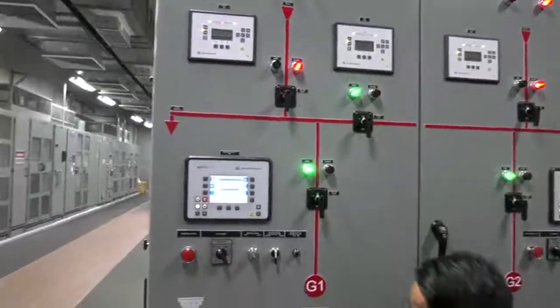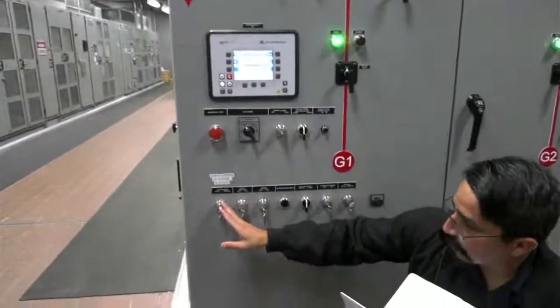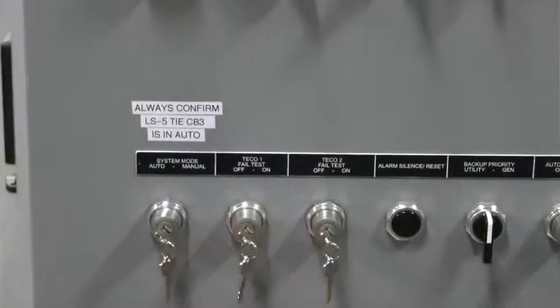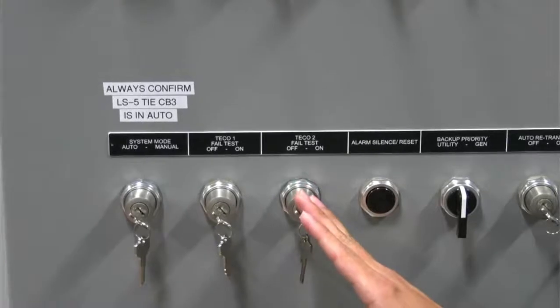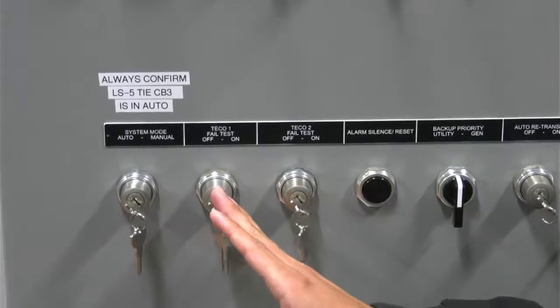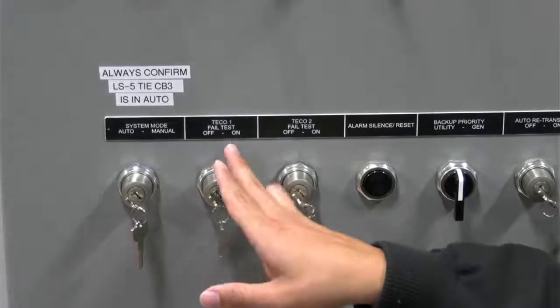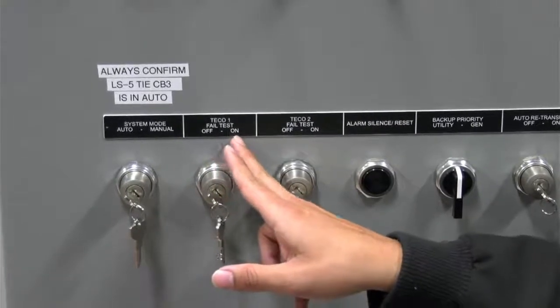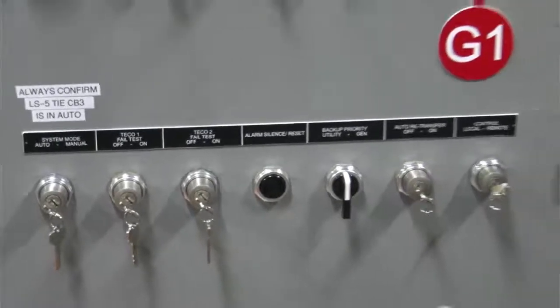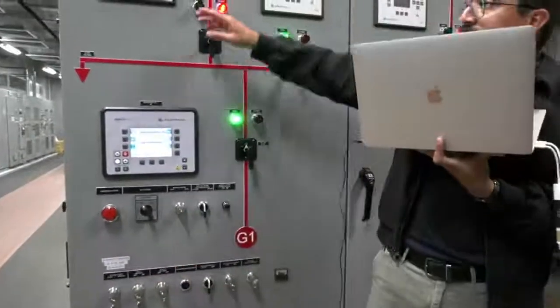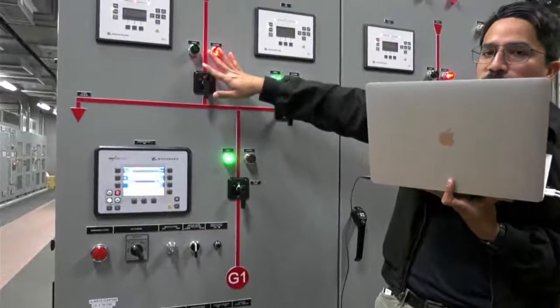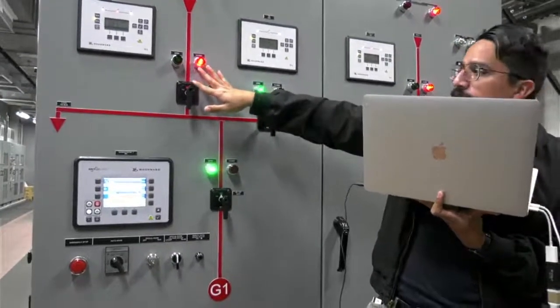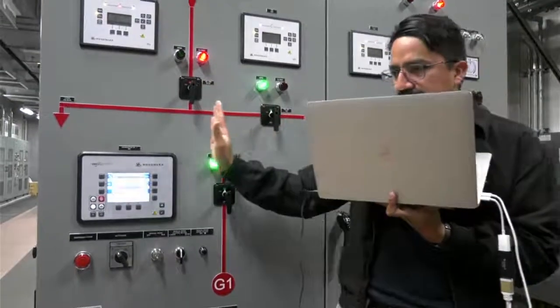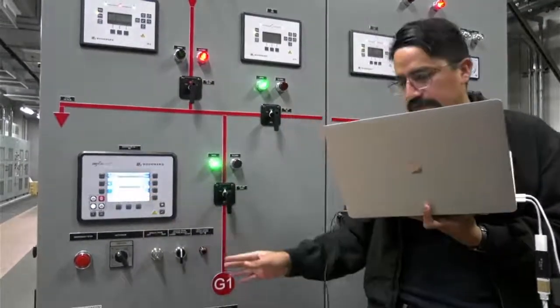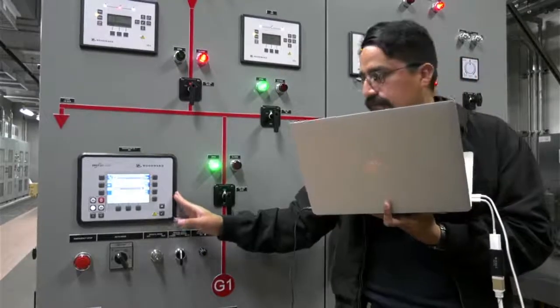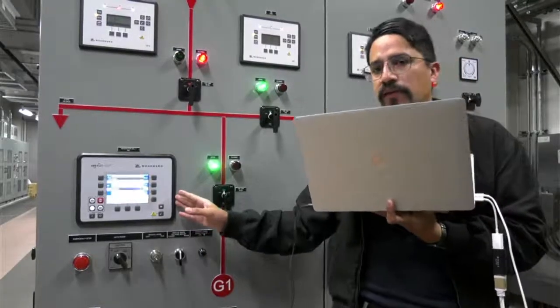Okay, so talking about group number 5, we have the system auto or manual. We have the 2 TECO fail test. What these switches do is, when you put one on, it tells the system to do the same procedure as if TECO 1 is failing, meaning this circuit breaker is going to open, right? And this side of the bus bar is going to be blacked out. The generator is going to run. It's going to go for a stable operation.